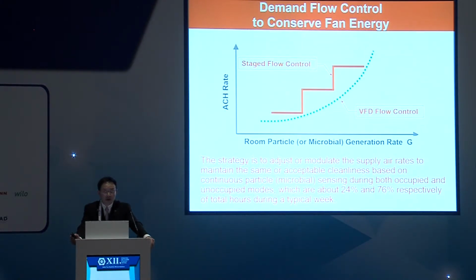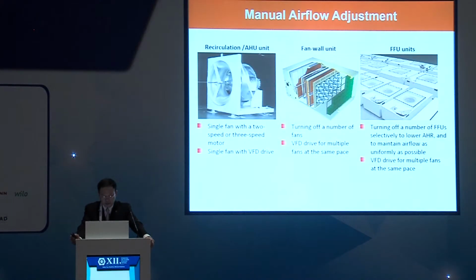There are typically two ways. One is to use staged ventilation. If you have a multiple fan wall, you can turn on a few fans and turn off a few fans to achieve different steps of ventilation level, or you can use a variable speed drive. If you use fan filter units or a recirculation fan, you can adjust the fan speed to achieve the fan flow modulation. Or if you use a fan wall concept, you have many fans mounted on a single section, so you can turn on a few of them and turn off a few of them to achieve different levels of stage.